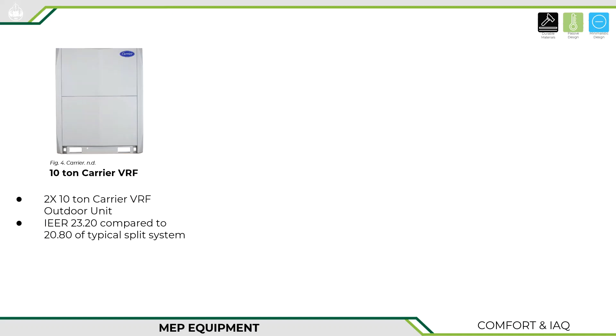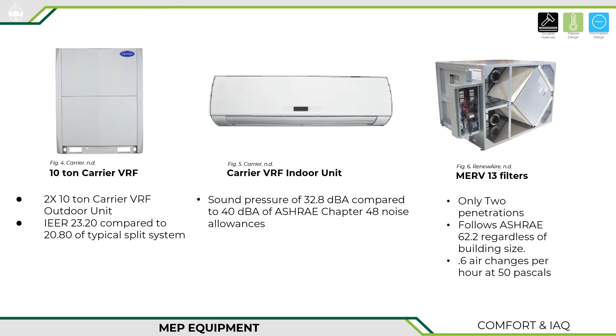Our heat recovery VRF shown has an integrated energy efficiency ratio, an IEER of 23.2, while typical systems earn a mere 20.8. Our team also chose a central ERV, reducing penetrations from 17 to just 2. All of the exhaust and supply ducts have been sized accordingly to follow ASHRAE 62.2. In an enclosed living community like this, where contagious disease can spread quickly, these kinds of systems ensure clean air and will reduce the risk of a building-wide infection.